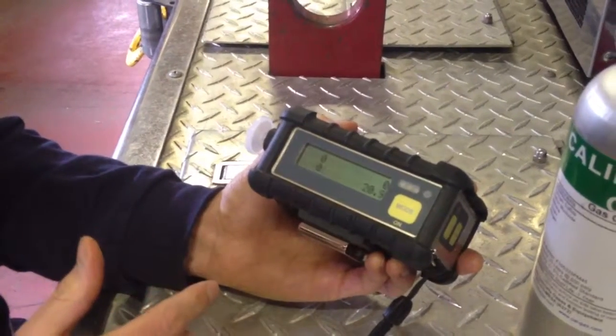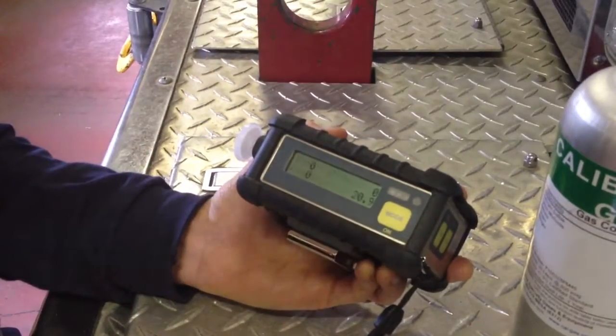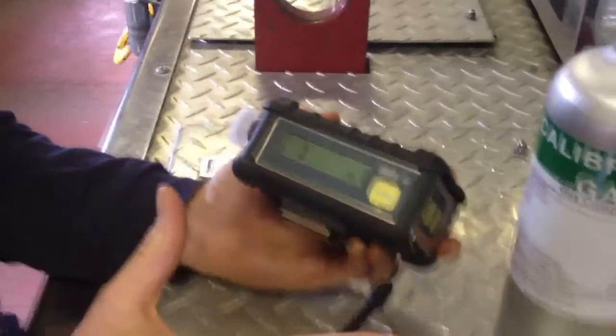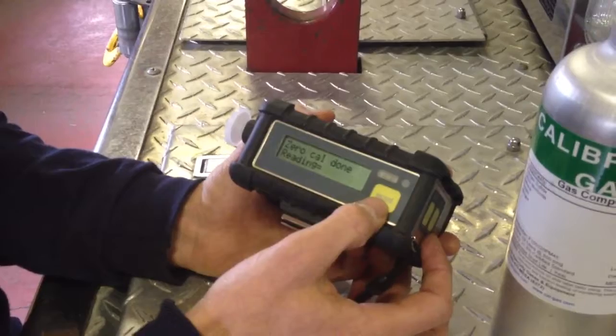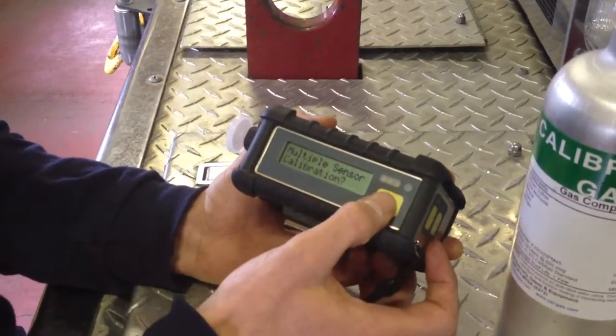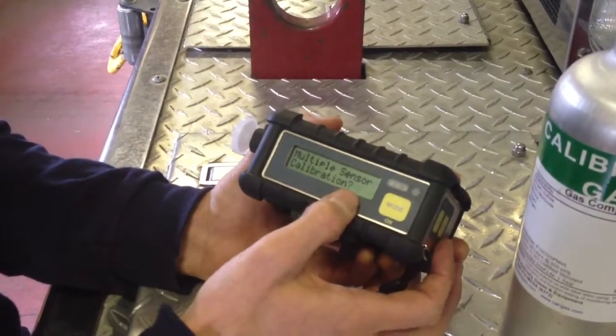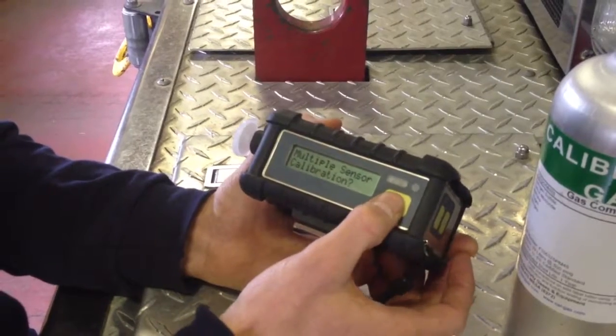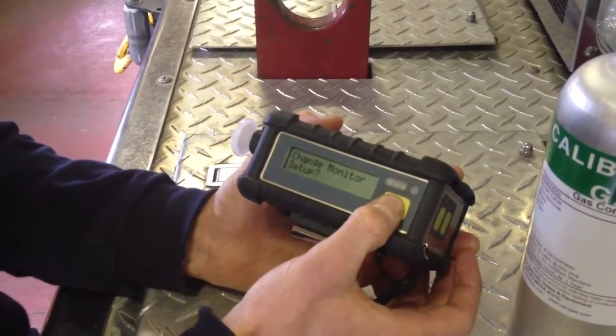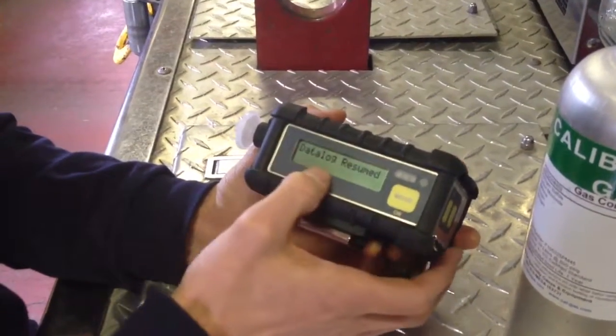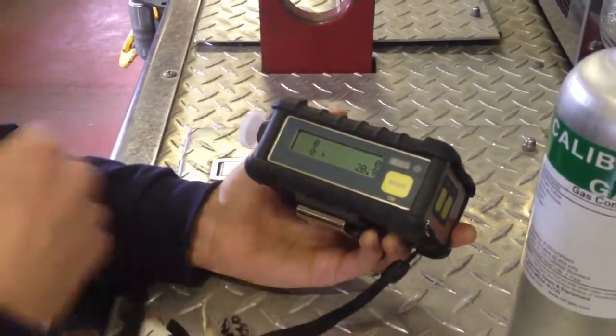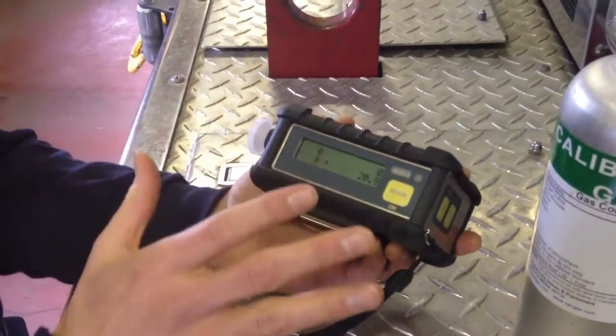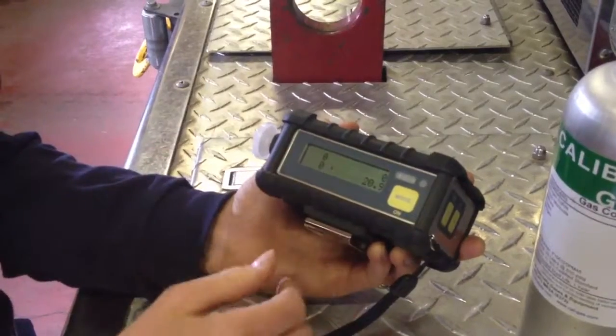Once it goes back, it'll say 0 cal reading done, and we're going to hit the mode button now. It's going to ask if we want a multiple sensor calibration, and we're just going to hit the mode button. We keep hitting it until it says data log resumed, which means we're out of program mode and back into the monitor.